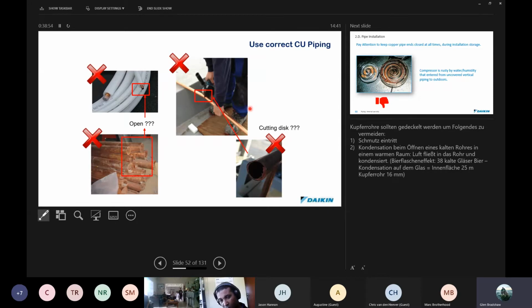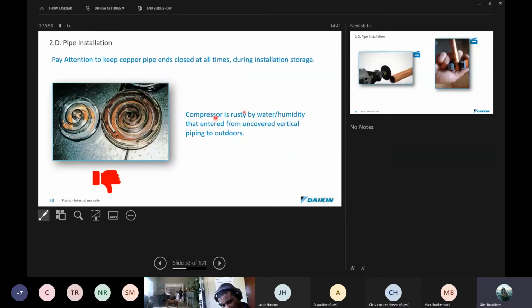If you don't close off piping and moisture gets into the piping, then this is the type of damage that can happen to a compressor. Here you can see that the scroll is actually rusted from the amount of water that entered into vertical piping that was not closed off on site. So it is very important that piping is closed off at all times. If you receive piping on site from a supplier, you're well within your rights to send it back if it traveled on the bakkie and was never closed up. I've seen bakkies driving around from suppliers with piping where the caps have come off.